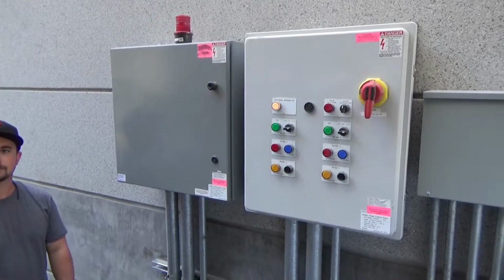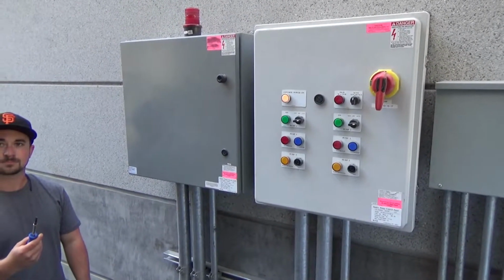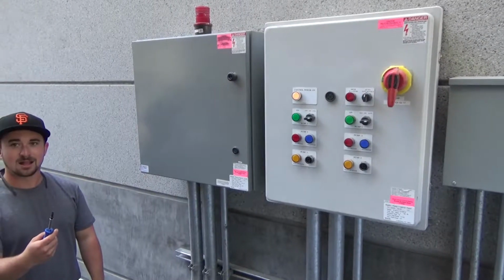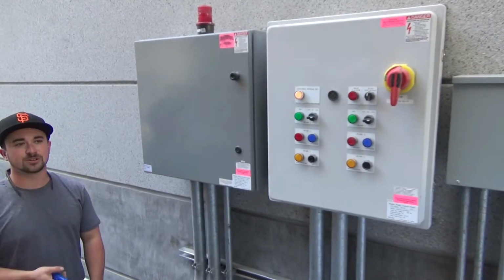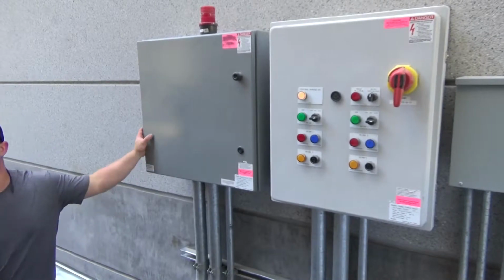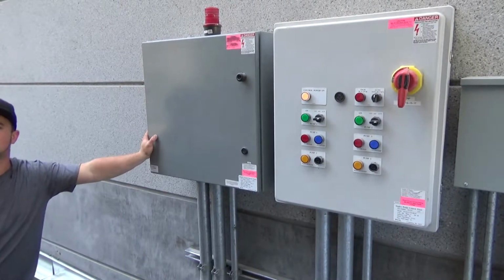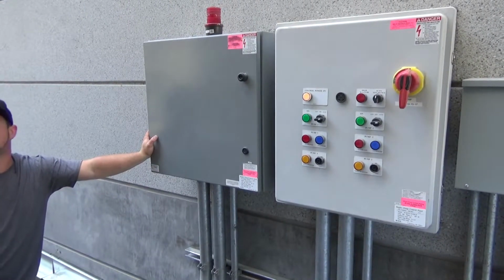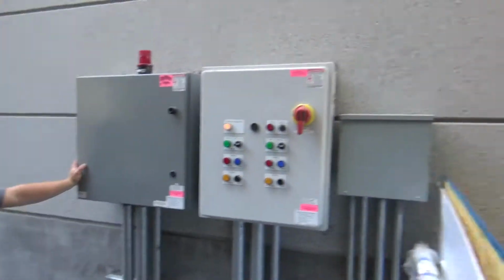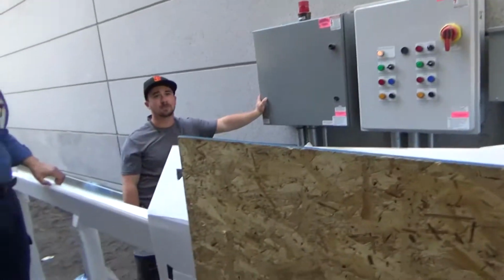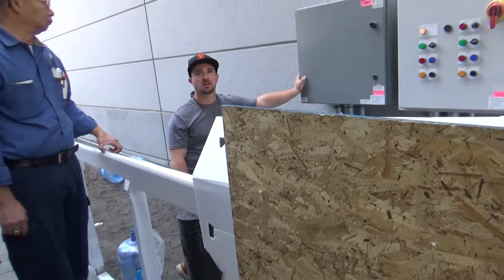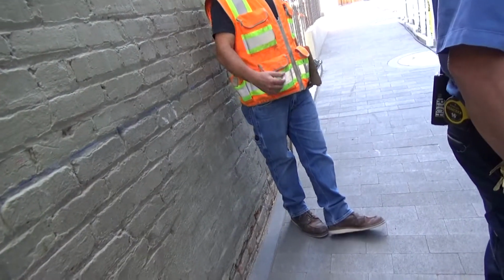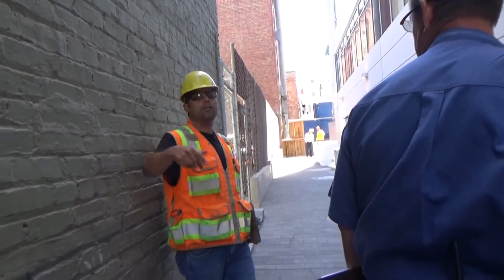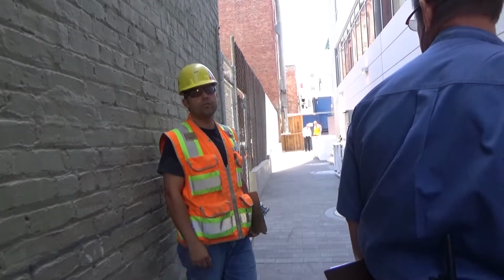And if we have to work on the pump, that's a confined space entry? Correct. We're not allowed to go in there. Anytime we do startup, we can't go in either because it's part of confined space certification. You have to have the whole training. A couple of people, the rack that these guys have set up, CO2 meters and all that good stuff. You need a blower for fresh air, an O2 sensor, a retrieval harness, and a competent person who is also trained.